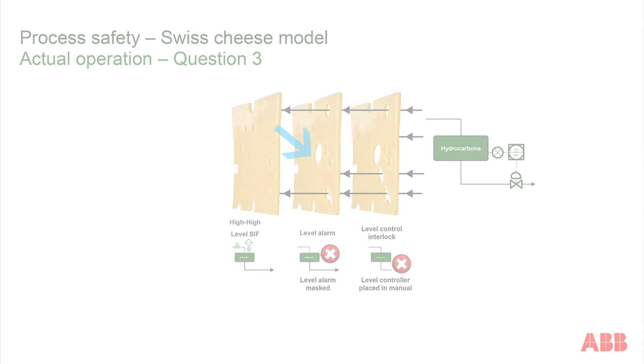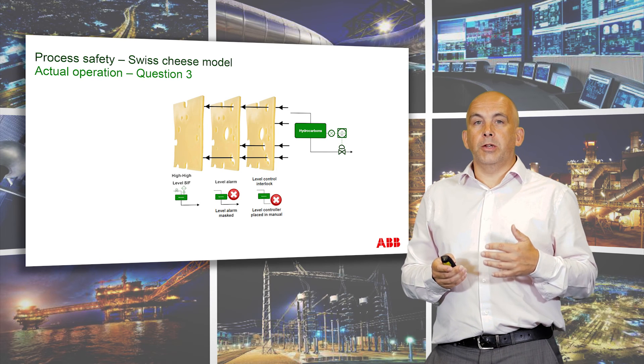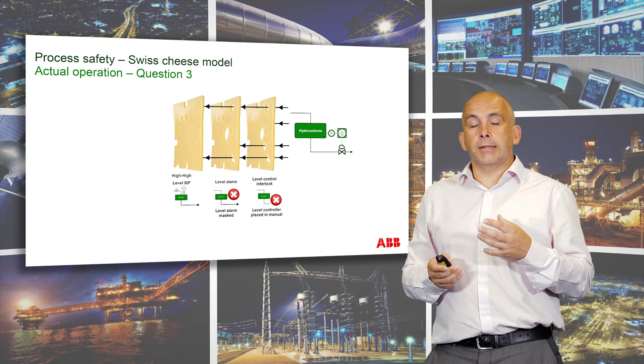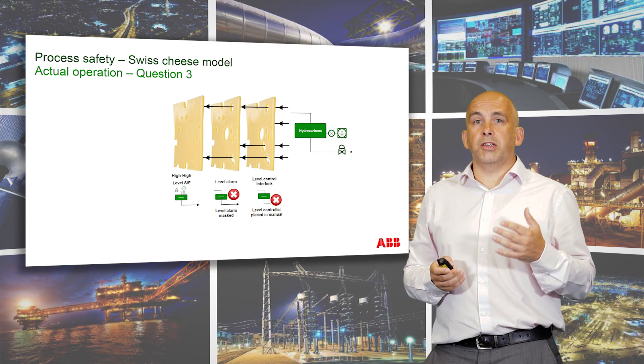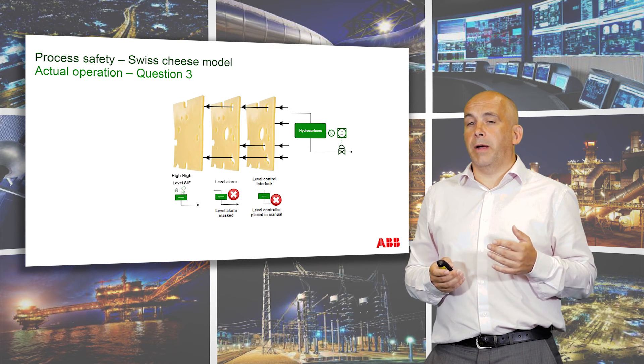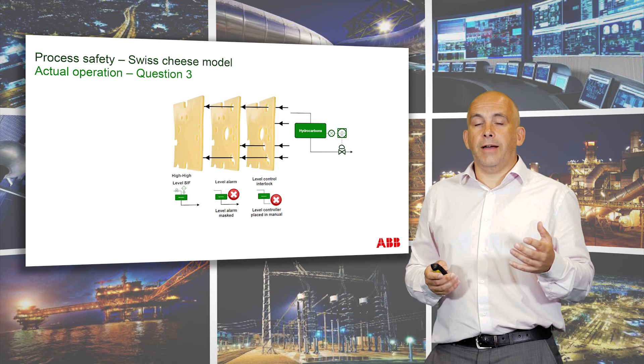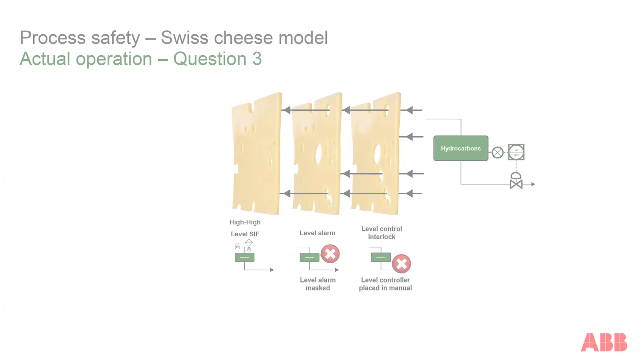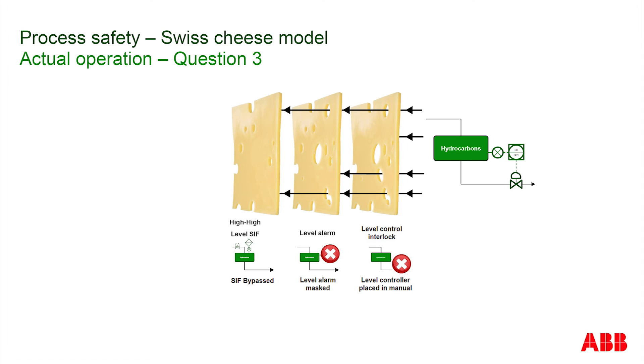Sometimes later, a maintenance person comes along to do a maintenance task called a proof test on that final barrier. To do that task, they have to bypass or override that particular safety instrumented function. As soon as that override is placed, the third barrier becomes ineffective.